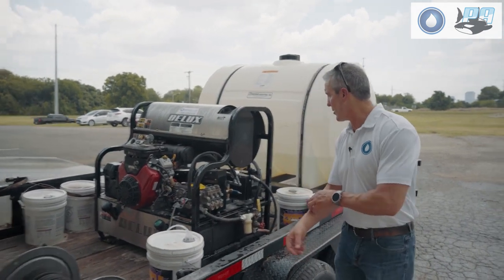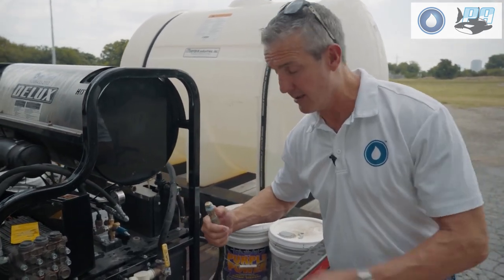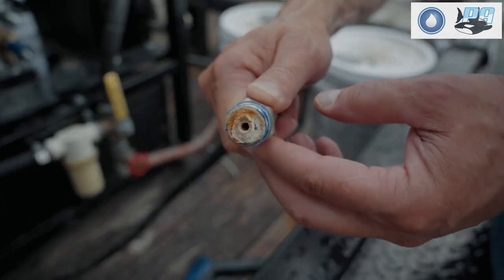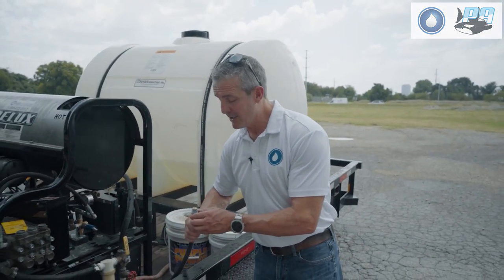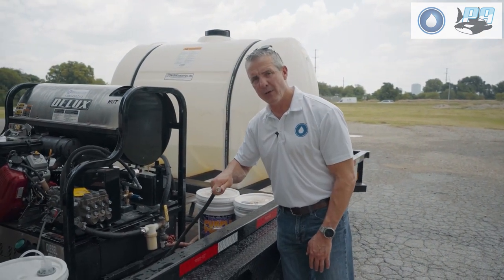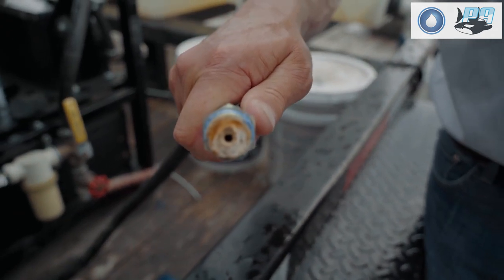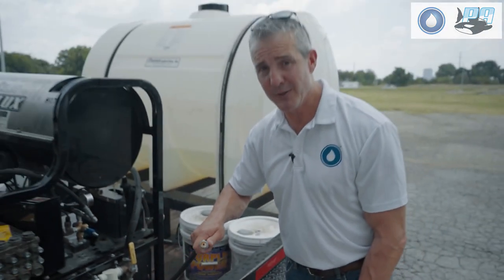I'm going to show you on the outside of the coil here. I've already broken this line loose. I'm going to show you how bad the restriction is. Take a look at this. That is normally a half-inch fitting that has a 3/8 hose on it, so it should have at least four to five times that much flow going through it as it does right now. This is all encased with deposits that have come from running a cheap soap that we would not recommend you use in your machine.